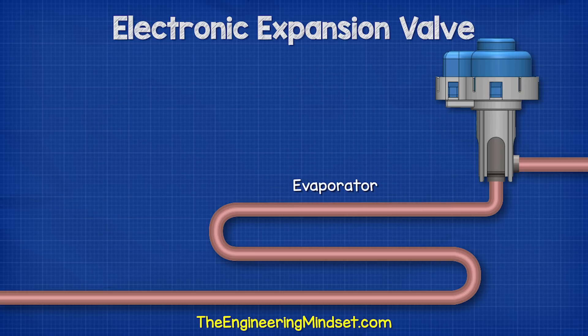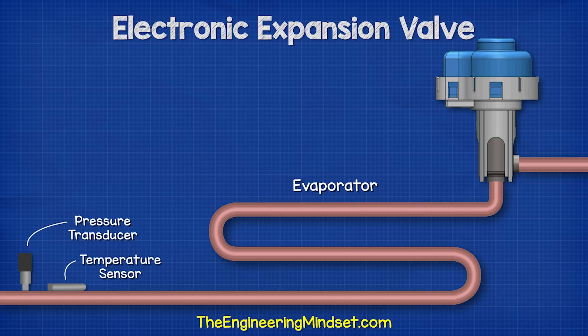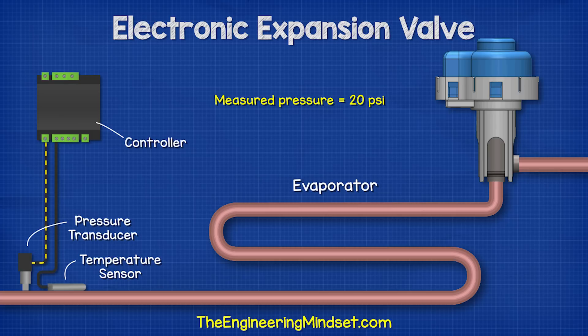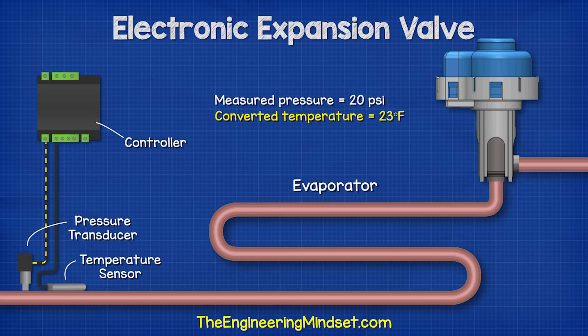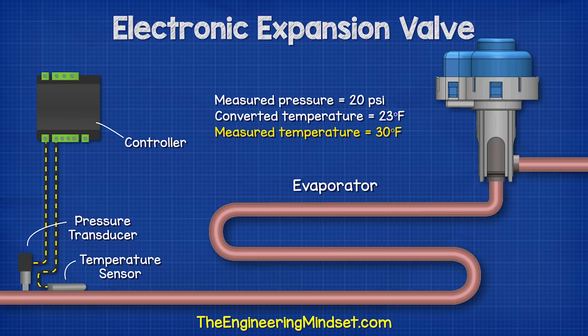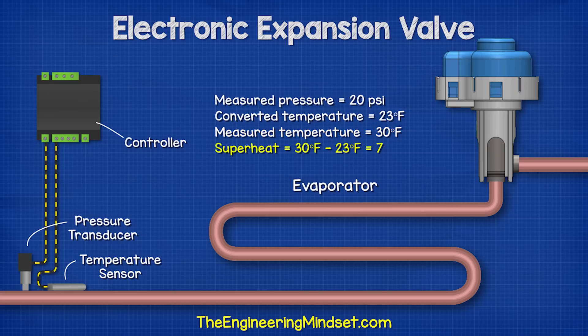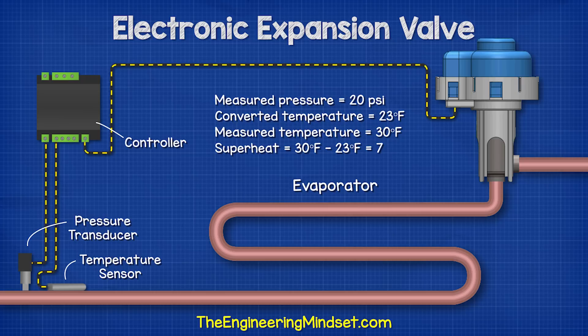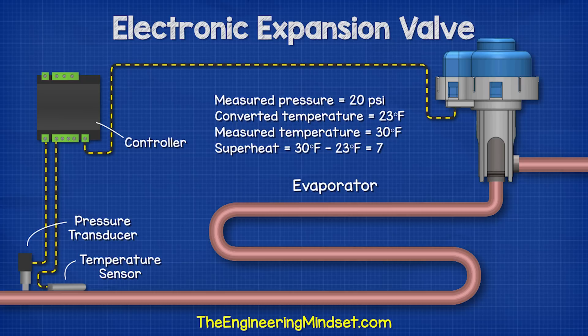At the outlet of the evaporator we find a temperature sensor and a pressure transducer which are constantly measuring the refrigerant. The controller reads this signal and converts the pressure to find the saturation temperature of the refrigerant using refrigerant data stored in the controller. The pressure reading is converted into its equivalent temperature for that refrigerant. This is then compared to the actual temperature being measured. The difference between these two is the operating superheat. The controller then decides if the valve should open further to allow more refrigerant or close slightly to reduce the amount entering.